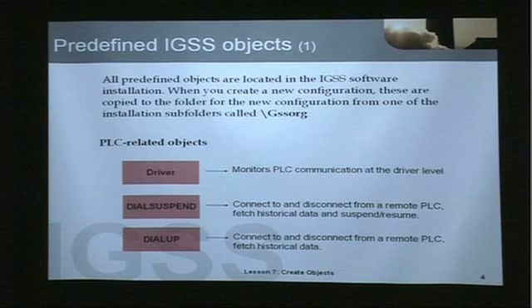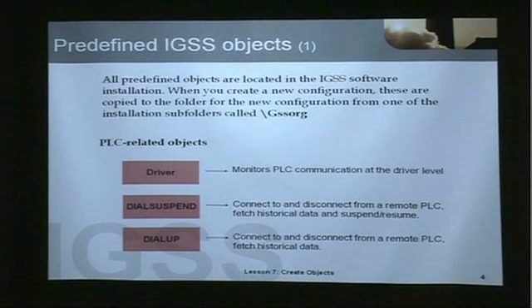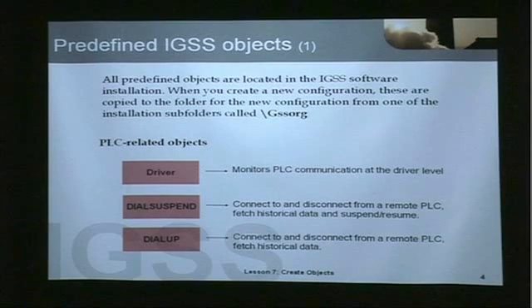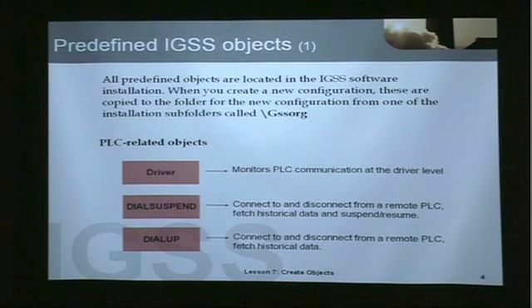Looking at the PLC-related objects that are predefined: the first is the driver object, which monitors PLC communication at the driver level. The second is the dial suspend object, and the third is the dial-up object. These are used in connection with remote communication to PLCs away from the plant, where historical data is brought into the system at predetermined times through a modem connection.